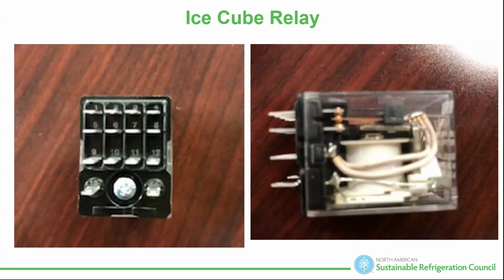I appreciate you saying that, because one thing I always like to remind mechanics, especially the younger guys, is when you're looking at a wiring diagram. I know personally when I was a baby learning this, I struggled, and when I was in the Army, wiring diagrams are drawn a certain way, and I don't care who the OEM is, this is when the angels sang for me. Drawings are drawn in the de-energized position, they are off. So as the technician, you have to energize the circuit in your head as you're running through it with your meter looking for the circuit.